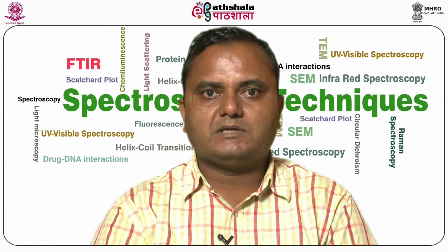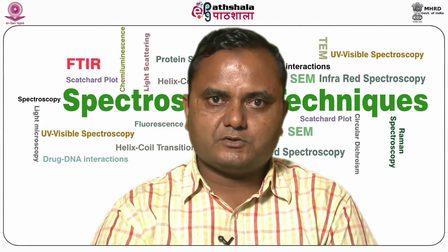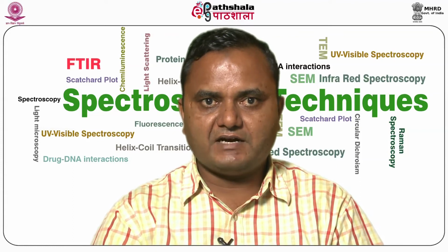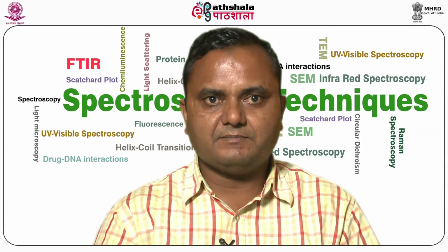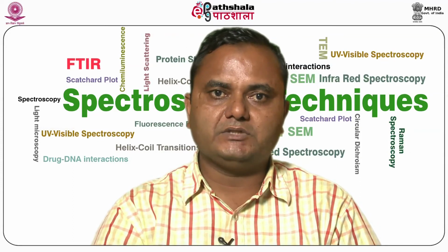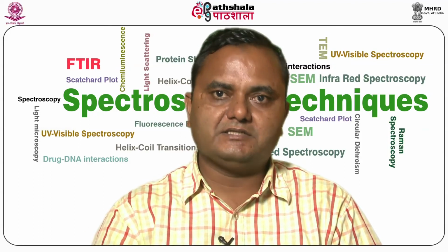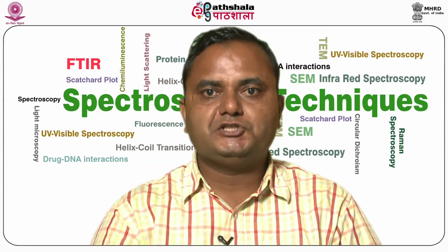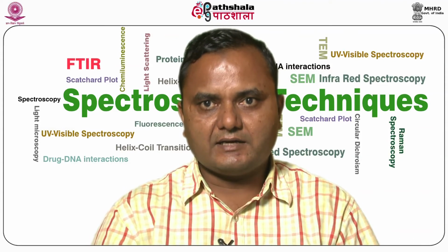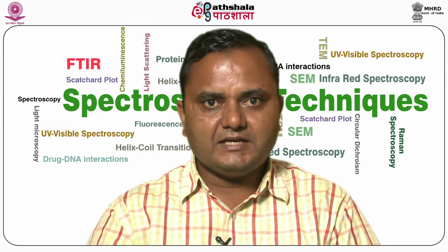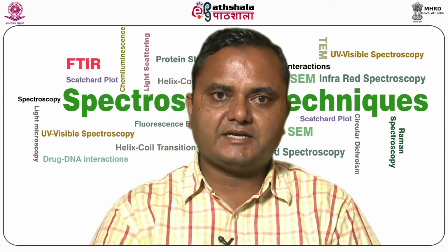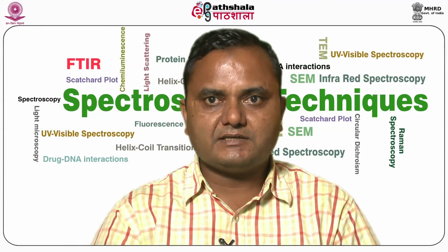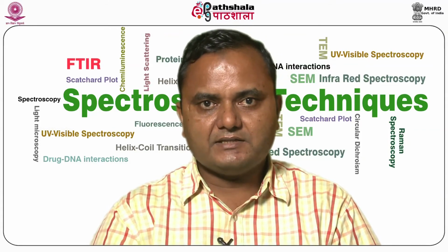Now we talk about electrothermal atomic absorption spectroscopy, in which the sample is contained in a heated graphite furnace. The furnace is heated by passing an electrical current through it, and thus it is named electrothermal. To prevent oxidation of the furnace, it is sheathed in a gas. Argon is generally used. There is no nebulization. The sample is introduced as a drop, usually 5 to 20 microliters of slurry or solid particles.